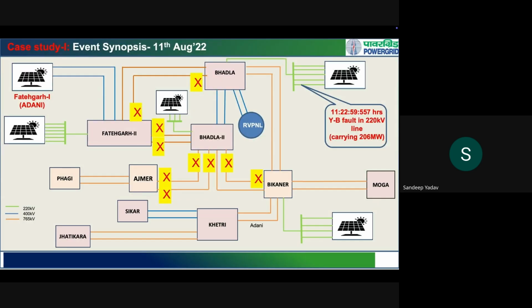renewable sources. So this is from the initial days, a snapshot of a system in western Rajasthan, in the northern part of India. Mostly, if you see the substations, these are large pooling substations where more than 10 or 15 wind farms and solar generators are connected. So Bhadla, Fatehgarh, Bhadla 2, these are all pooling stations where more than 3,000, 4,000 megawatts of solar power is being pooled, and later it is fed through these 765 kV lines to the load centers.